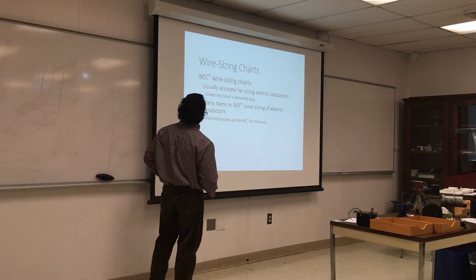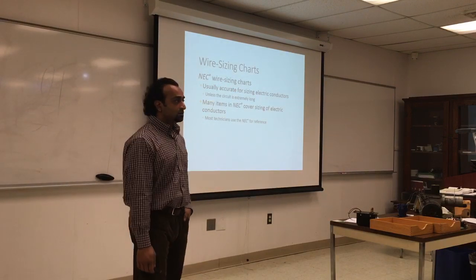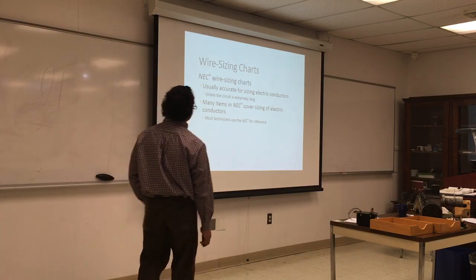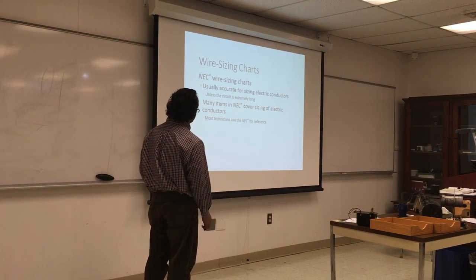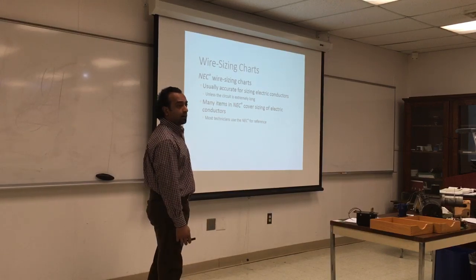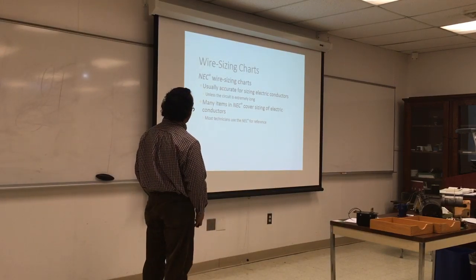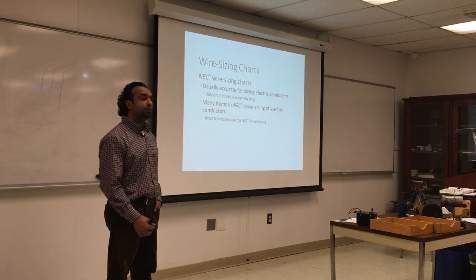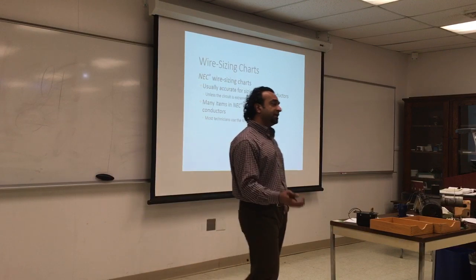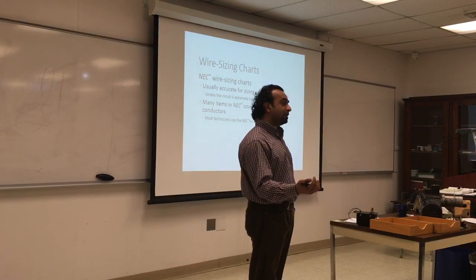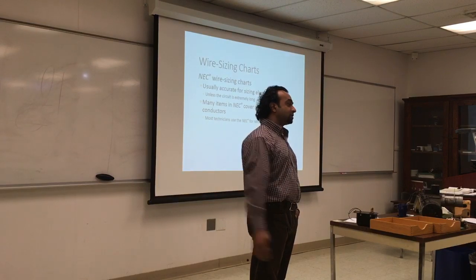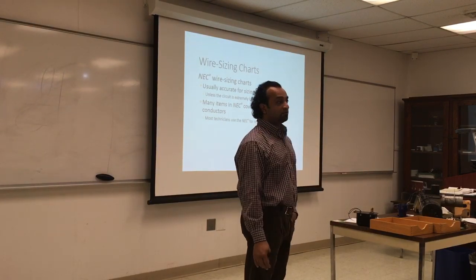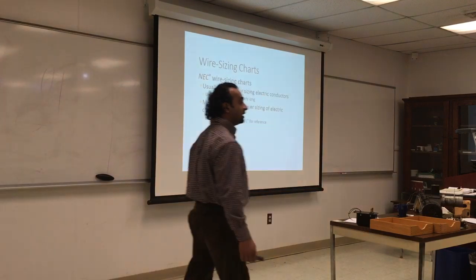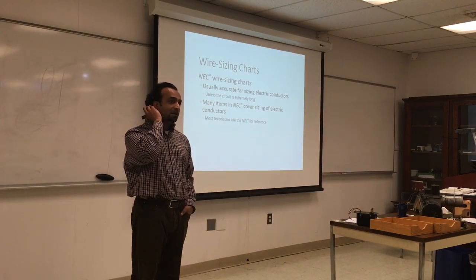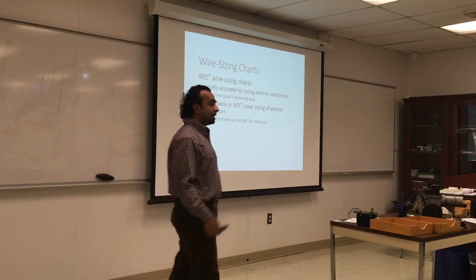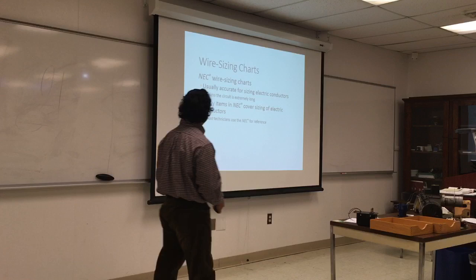Again, all wire sizing charts are based on the National Electric Code. So when in doubt, you always consult with the code. So usually, all conductors and all wires are sized within range, unless it's extremely long, and that's what usually happens with air conditioners when you have the condenser placed outside. Where do we usually put the condenser? Either outside in the yard, or sometimes, Louis said, on the roof. Put it on the roof because you want to be outside, exposing hot air to the atmosphere. Sometimes in big buildings you see them hanging. Yeah, I've seen that at the old people's place. But it has to be outside.